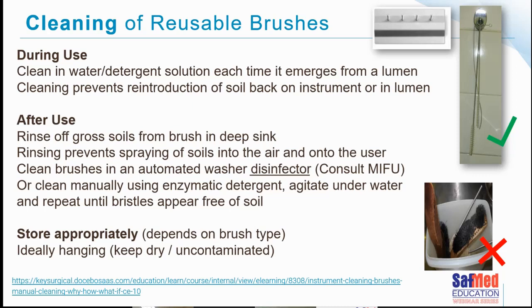After use, of course, it's important to rinse off all the gross soils properly in a deep sink. This prevents spraying of soils into the air. You want to do it under the water line. You want to follow the instructions for use from the person that you bought the brush from. If you bought the brushes from Clicks or Pick and Pay, then there will be no instructions for use because they weren't designed for medical devices. If you're buying a brush designed for a medical device, it will of course come with a set of instructions for use. And they will include, I'm sure, cleaning manually using an enzymatic detergent, agitating under the water, repeating the process until the bristles are free of soil, and hanging them up afterwards to dry.